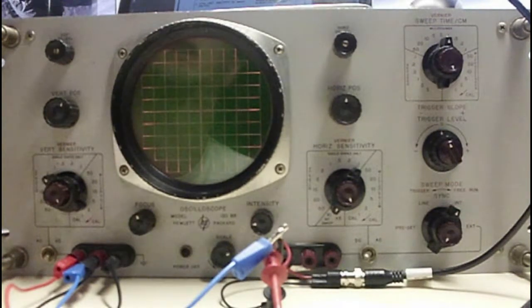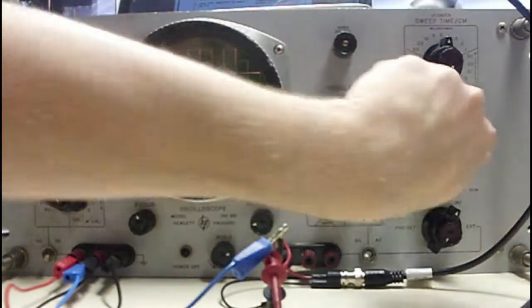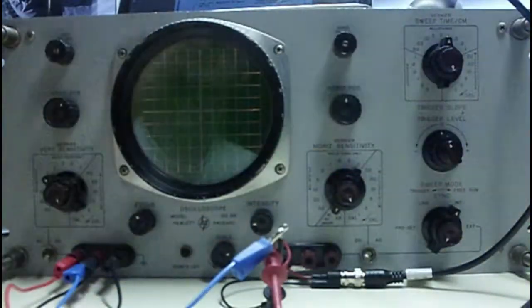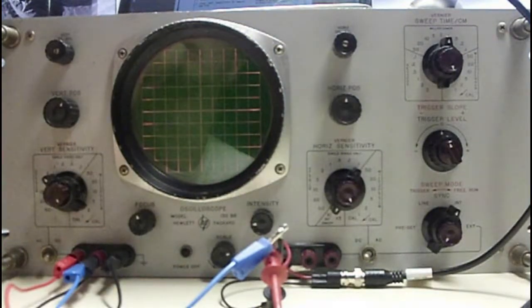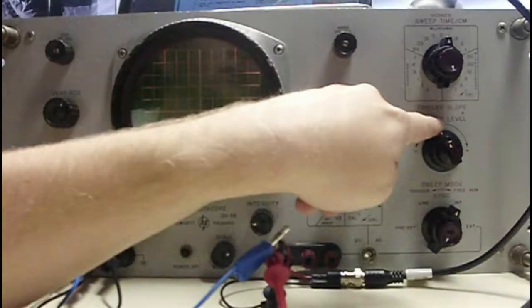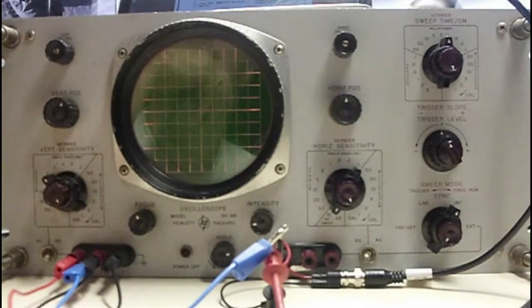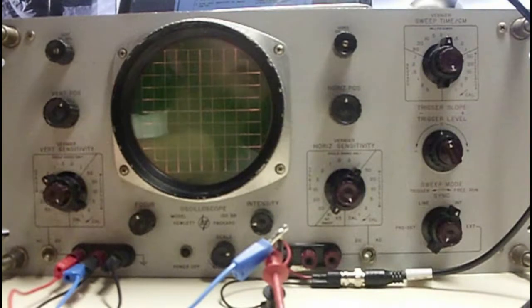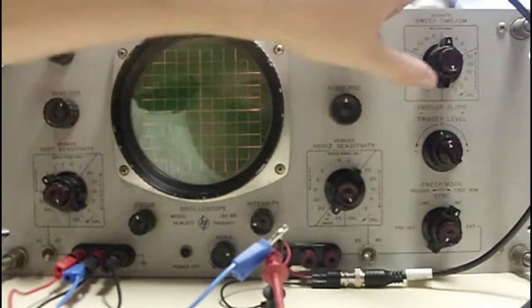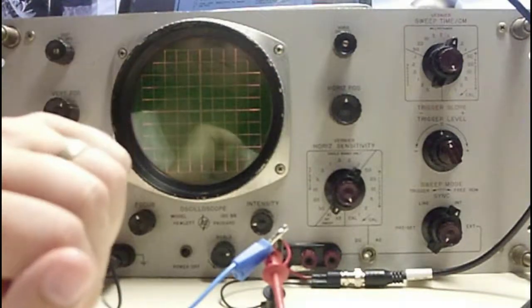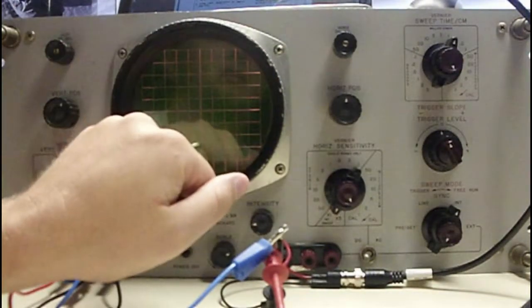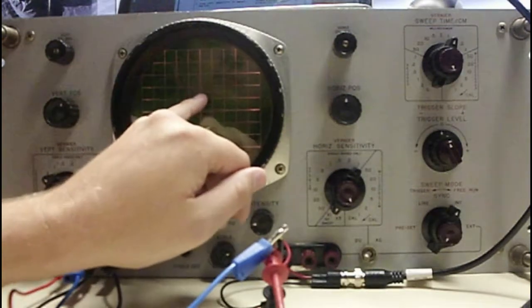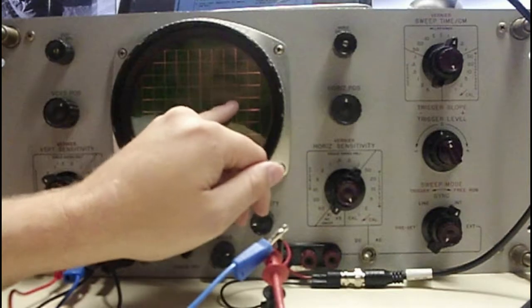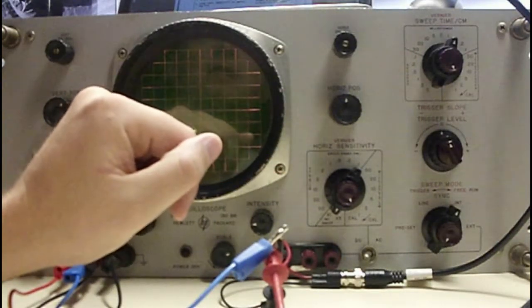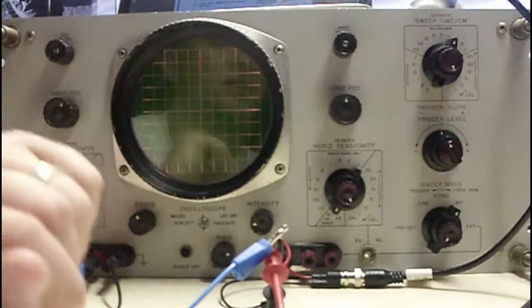And so now we're doing step 7, set trigger slope switch for triggering on positive or negative slope. It doesn't really matter. Set trigger level control to 0. So where's the trigger level control? Okay, so we've set it to 0. Select desired sweep speed. Okay, since we're at 1 kilohertz, let's set our sweep speed to 1 millisecond. And so we should be getting 1 cycle per centimeter here. Adjust trigger level to start trace at desired level.